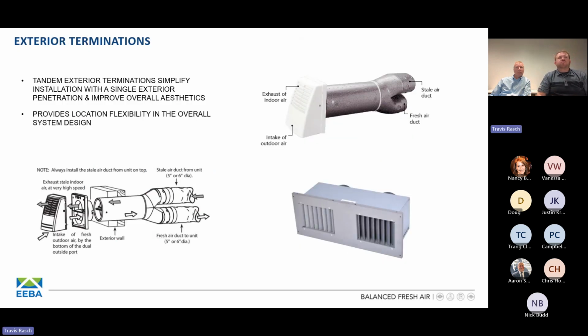I alluded to it before, as it relates to exterior terminations. Again, we've got to bring fresh air in from the outside to feed that HRV or ERV, and we've also got to take that stale air from that product and take it back to the outside. There are a couple different approaches to this. You could use two separate independent sets of terminations, again, having their corresponding need, or you could utilize what we call our tandem or concentric terminations shown here on this slide.